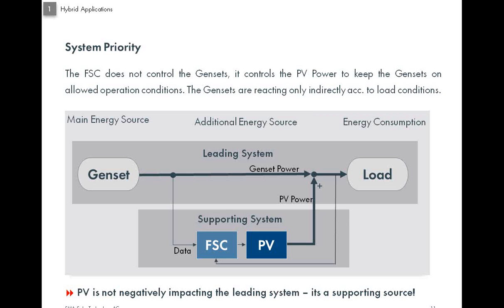So as you can see here, basically you have the genset which is supplying load, and the PV is also connected at this point. So considering the load requirement at any point, the FSC is directing the PV to increase or decrease the power as needed. So as you can see, we are not controlling the genset in any way. The only thing we are doing is taking one-way communication data from the genset. That's all.